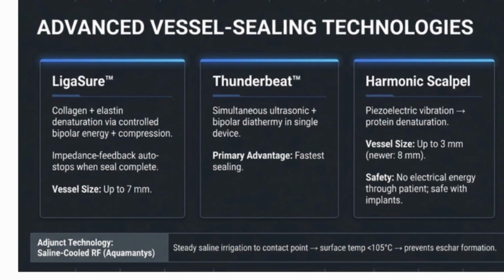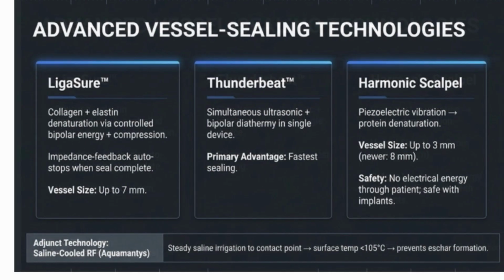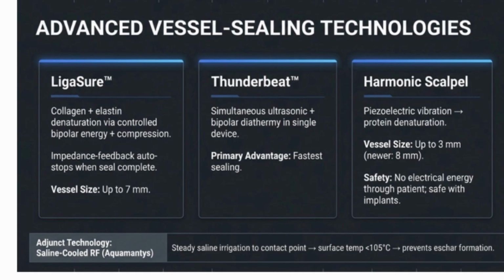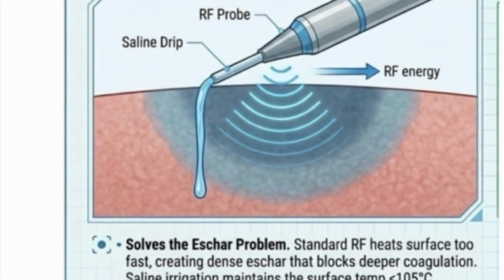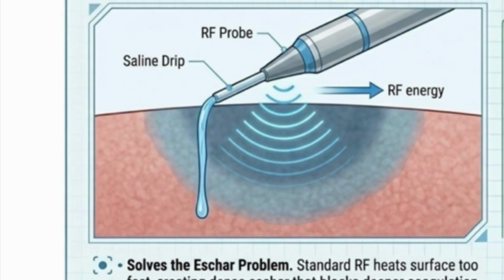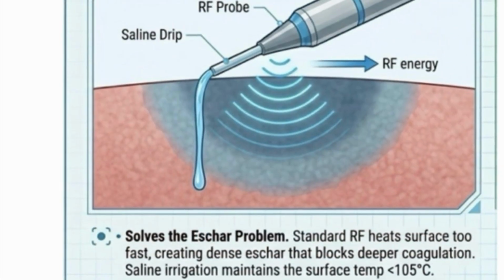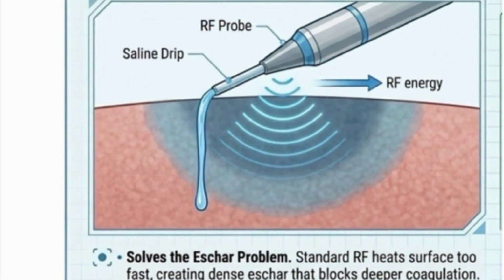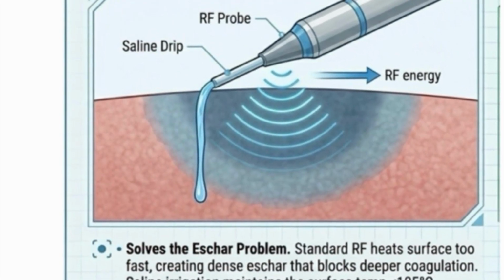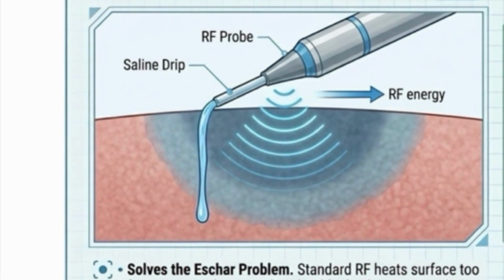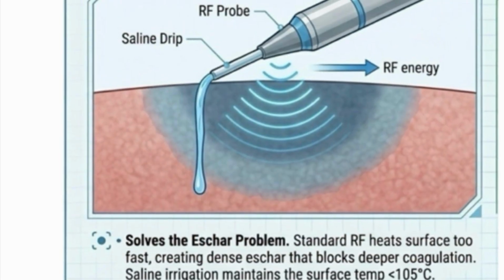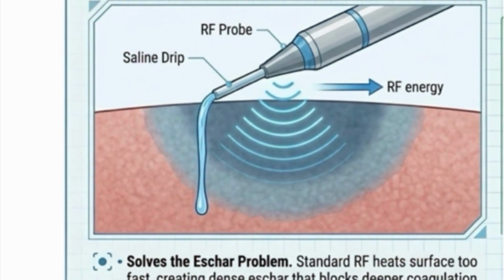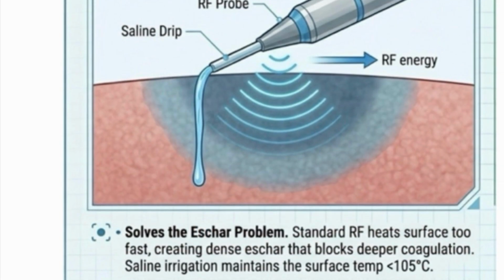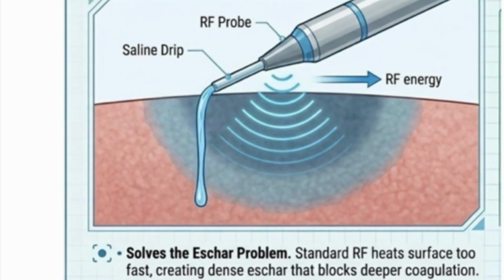The Thunderbeat uses both the ultrasonic and the bipolar diathermy in a single device. It is the fastest sealing method. The saline cooled radio frequency desiccators solve the problem of the eschar. There is standard radio frequency which heats the surface too fast, creating dense eschar that blocks deeper coagulation. Saline irrigation maintains the surface temperature of less than 105. The result is deep, constant coagulation of solid organ parenchyma without surface charring.